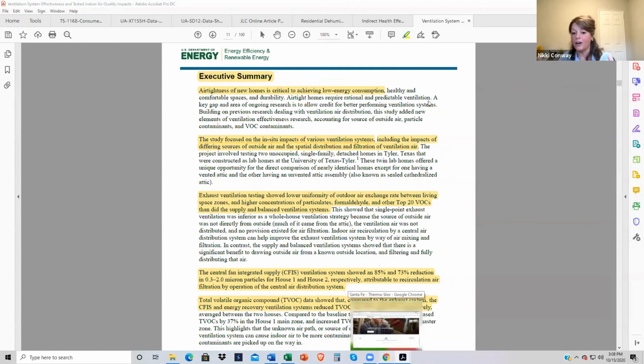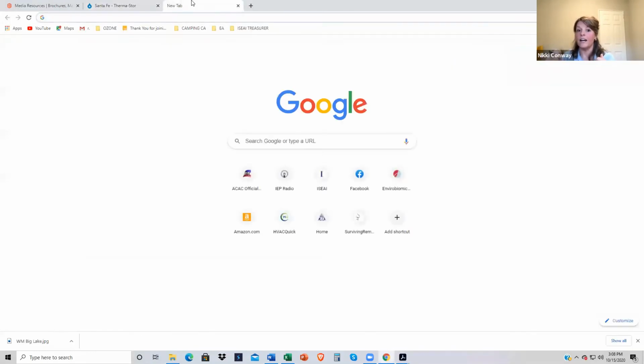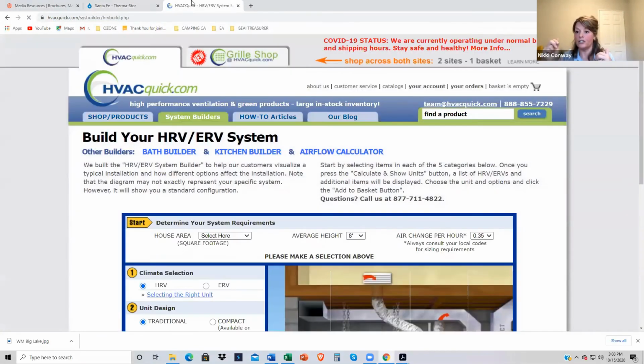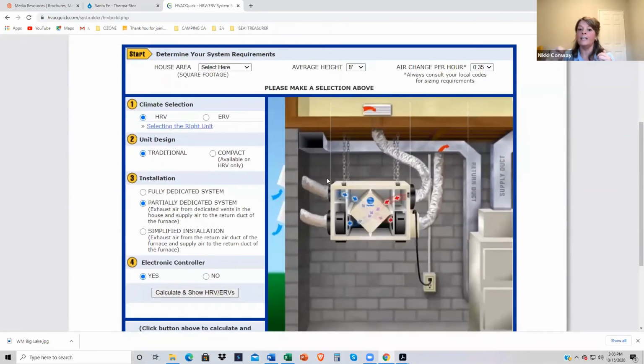And even some ERVs now, you can set up your balanced ventilation on the supply side to be a little bit more positive. You can put a damper on there, and they have different fans, then put a damper on there. So we can try to get a positive pressure, which is very important in our humid climates.